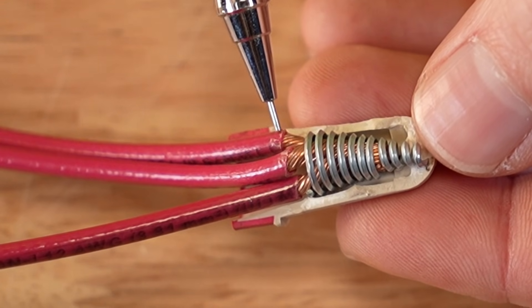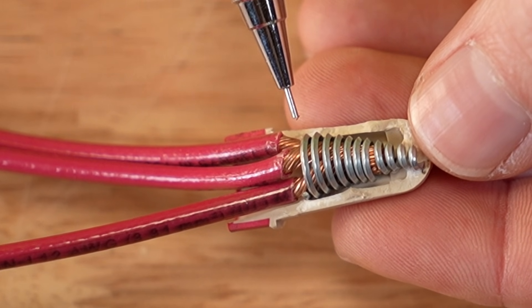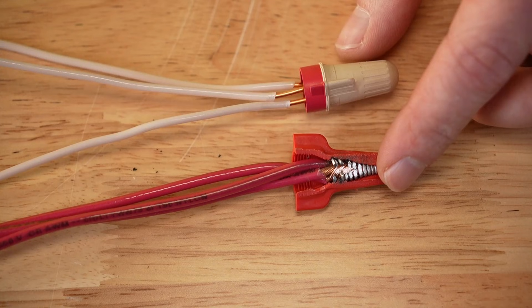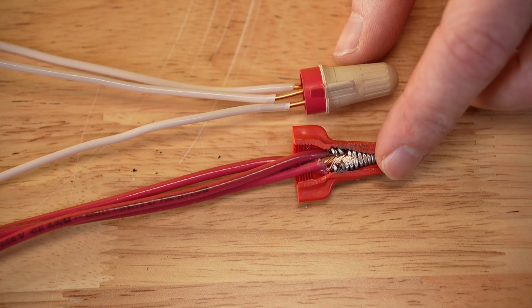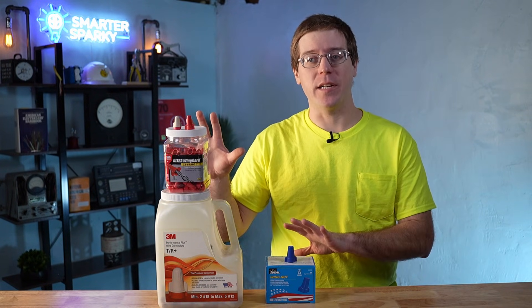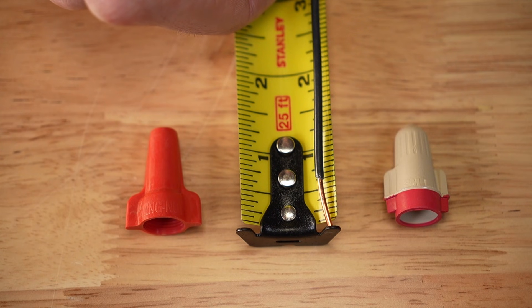Most wire nut problems don't start at the wire nut. They start before it ever goes on. It's crucial to strip the insulation back far enough that the bare conductors come into full contact with the internal spring in the wire nut, but not so far that the bare wire is hanging out past the bottom. No insulation should end up inside the spring, and no copper should be visible outside of the wire nut. Strip length varies depending on the size of the wire nut. For these mid-range wire nuts, about 5 eighths of an inch is the sweet spot.